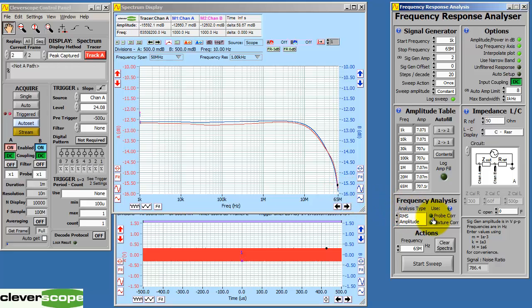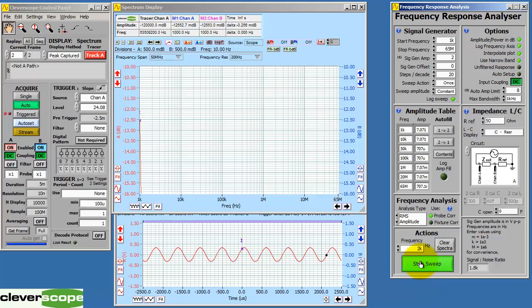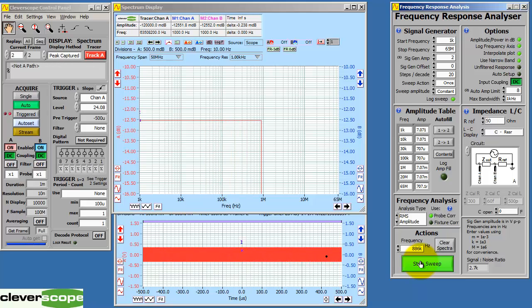Now we turn on probe correction and we redo the sweep. Now you can see the sweep is flat all the way from 1 kHz to 65 MHz. In this way you know that the RMS levels that you are measuring are correct and not varied by the output signal generator level or by probe impedance. Again, we commend the BNC calibration procedure to you for your use in measuring components and systems.